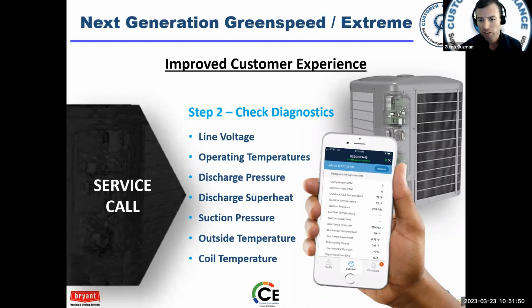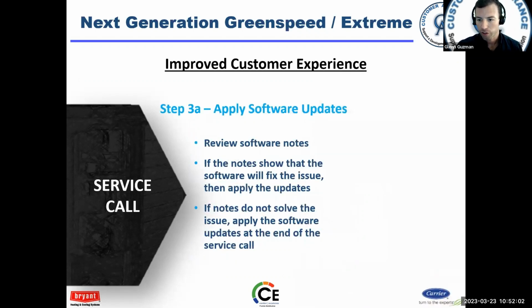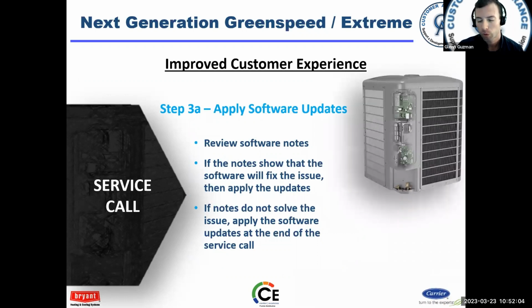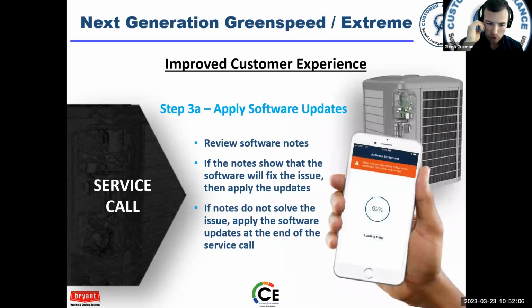This information is vital when you're diagnosing what's wrong, especially line voltage, operating pressures, superheat, that sort of thing. You can also look at the software notes. When the unit first came out, there were some issues that a software update resolved. It's been a while since that occurred, but maybe there's a software update that needs to be applied, and that's why it's not working properly. So you can check and review that.